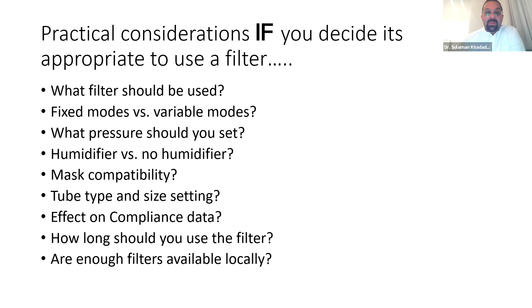So I think at our lab, thanks to my techs, we've been doing a lot of data. This is older data, and I'm sorry, it's again short notice, didn't have time to label everything. So when you use a fixed mode, and this is just 3 machines that we ran on different pressures, there's a difference of about 0.5 to 1.5 in terms of centimeters of water between the set pressure and the measured pressure.